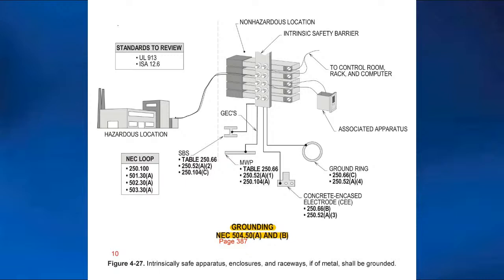If it's not an electrode, then you've got to apply 250.104 C. And if the water pipe is not an electrode, you'd have to look at 250.104 A1. You have to look at those to see if they're an electrode or they're not an electrode.